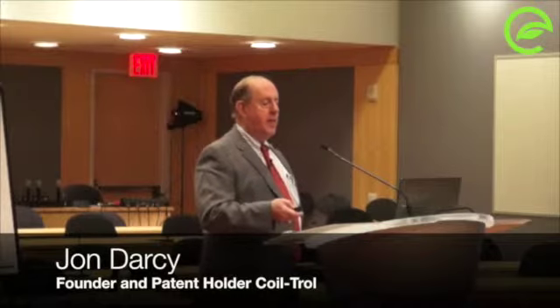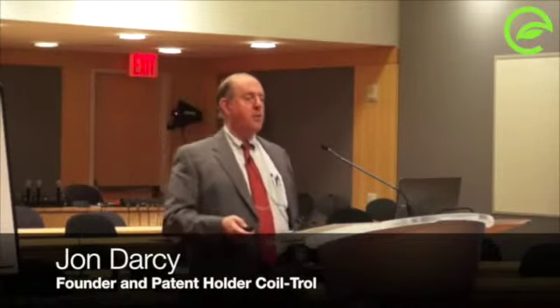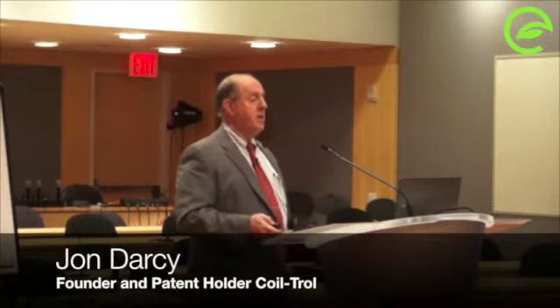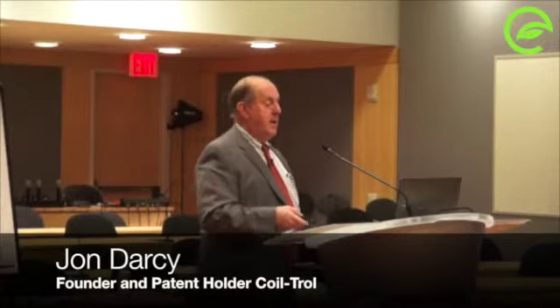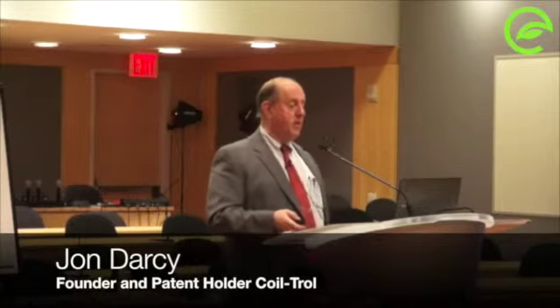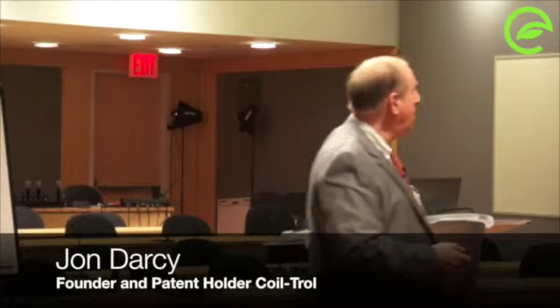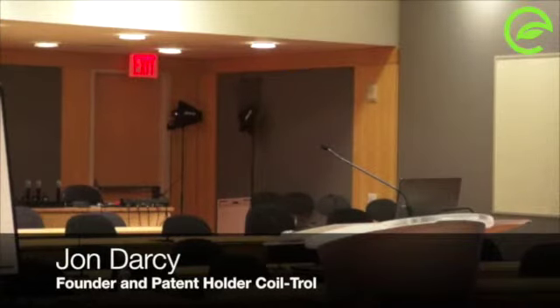That's what laminar flow looks like. This is a pictorial of what turbulent flow is, and it literally looks like that inside the coil. This is a performance factor where you can see that at 20% of coil flow, which runs across the bottom, we have 50% of the sensible heat. Now, we just said we can't get to 20% of flow because none of the coils will throttle back that far. And at 50 percent of flow, the latent still isn't satisfied. The latent isn't satisfied until you get all the way out to 100%.